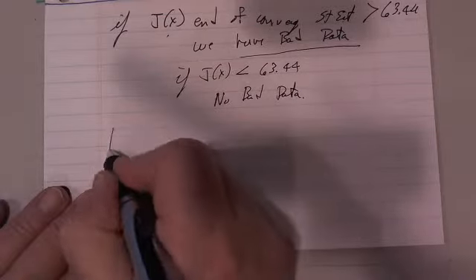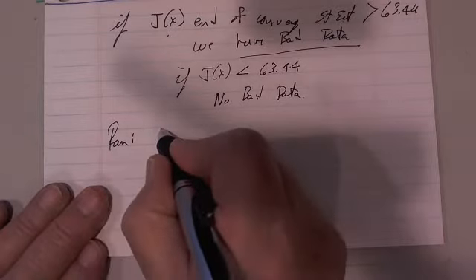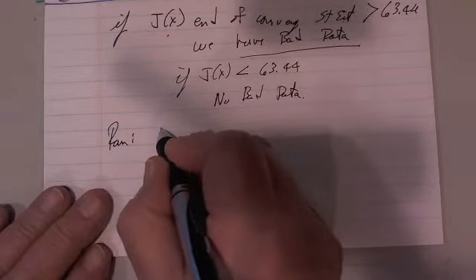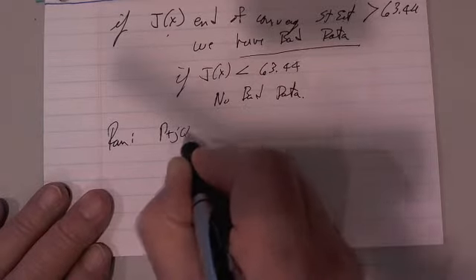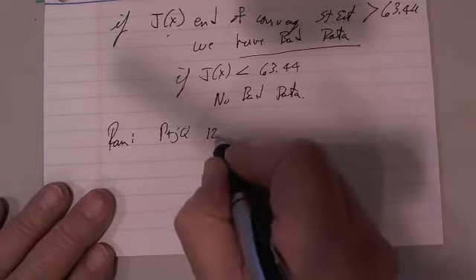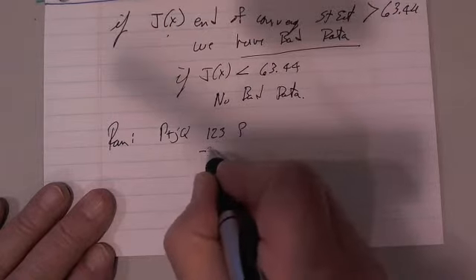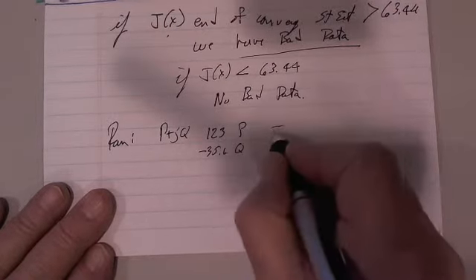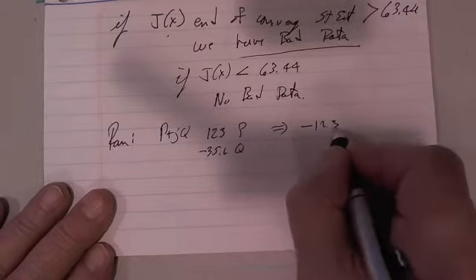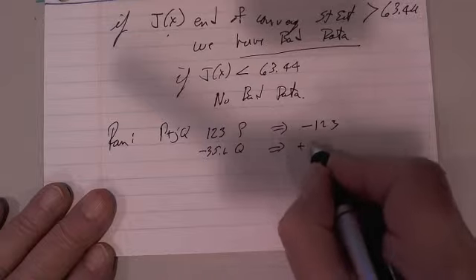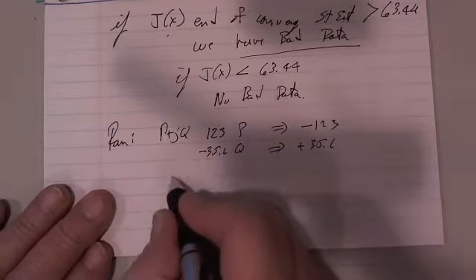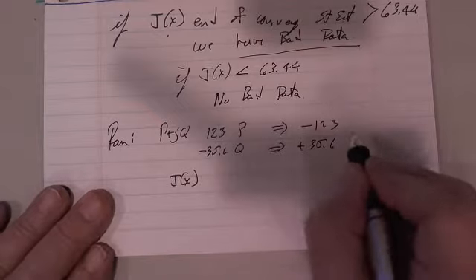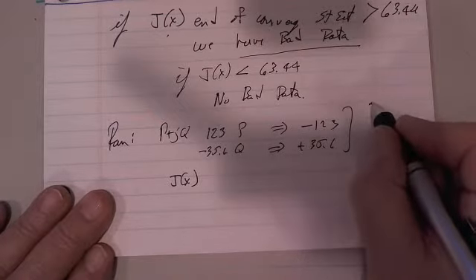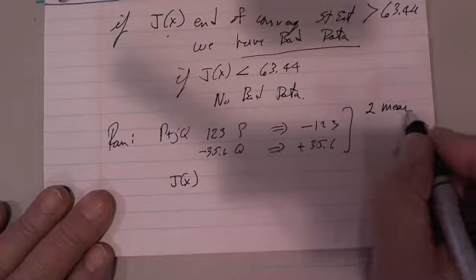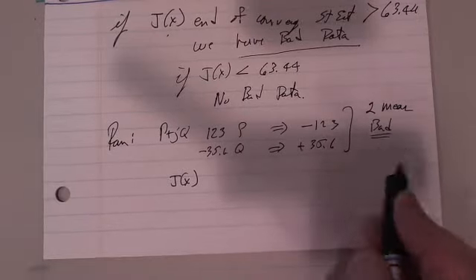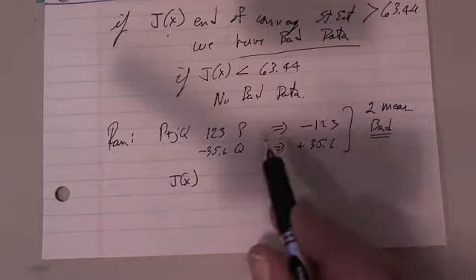I ran the state estimator from the book, took a P plus jQ measurement, which was 123 for the P and minus 35.6 for the Q, and changed it to minus 123 and plus 35.6. Just changing one measurement actually counts as two measurements being bad.